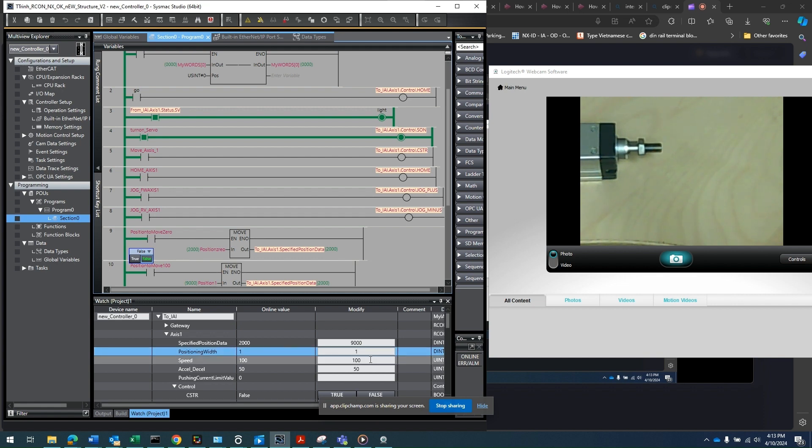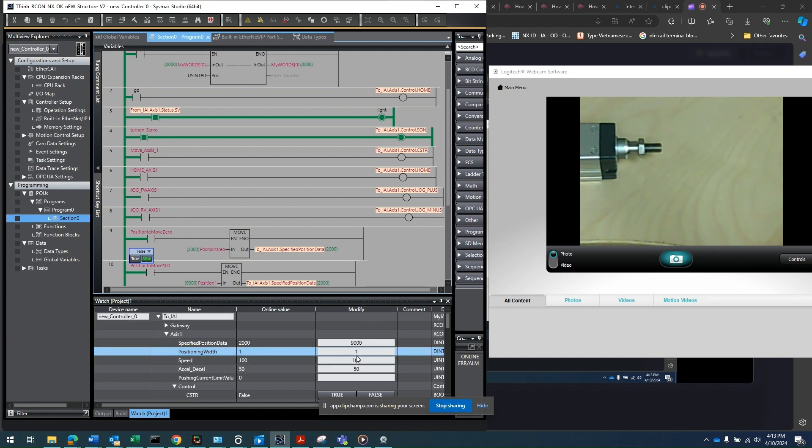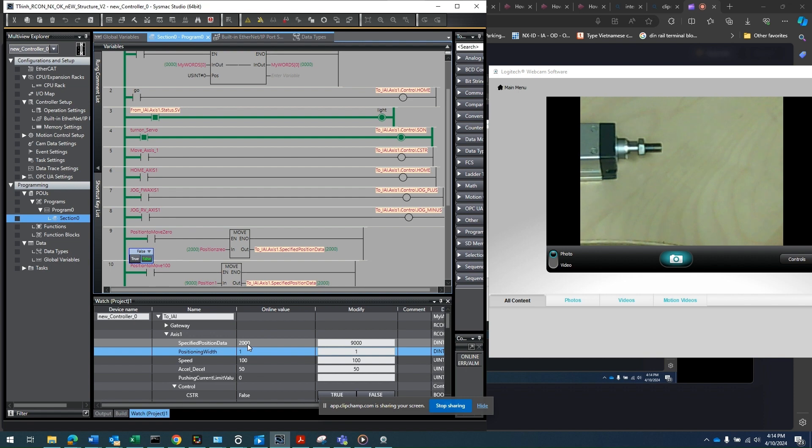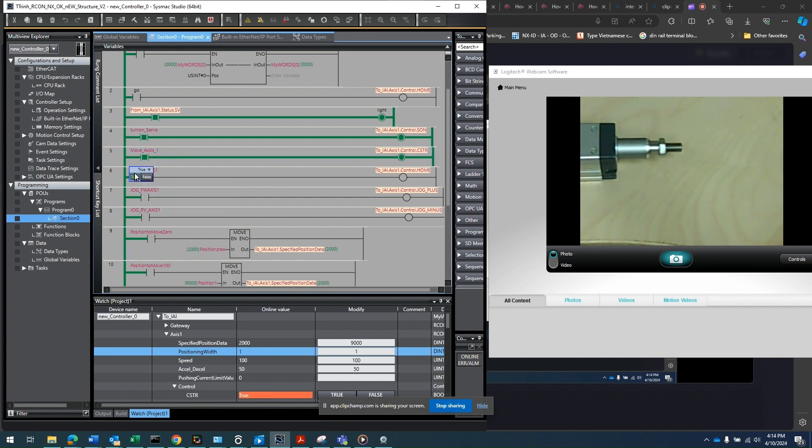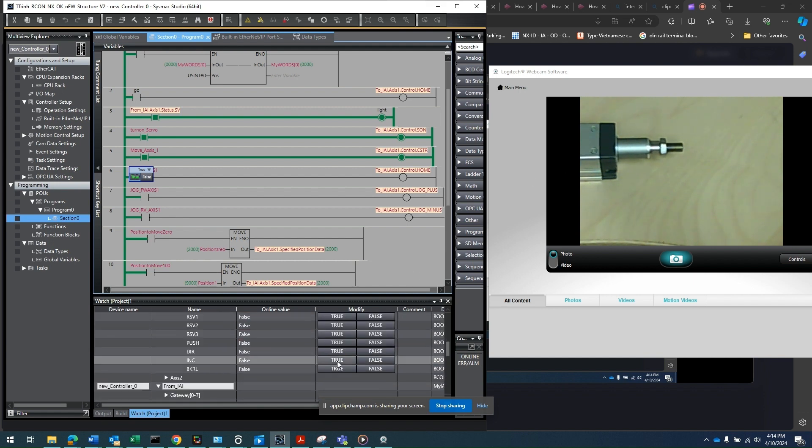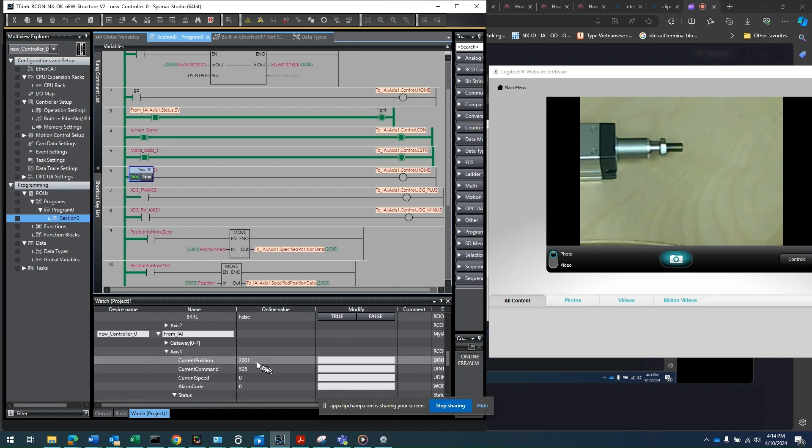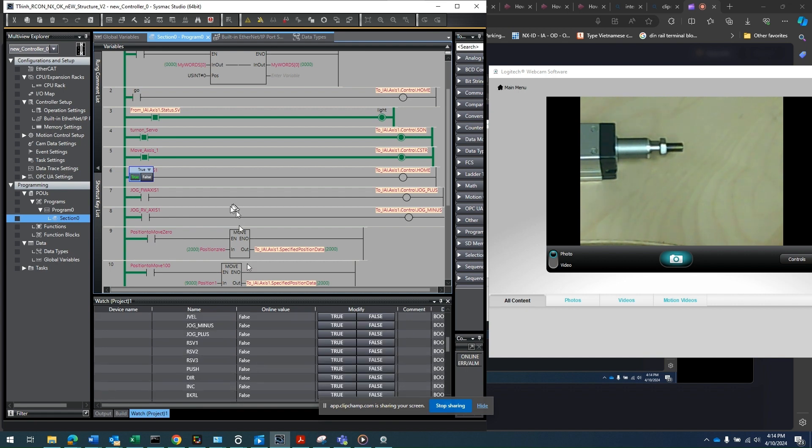You need to have some speed in here. This is in millimeter per second. I have 100 millimeter per second in there. Now I have 50. That means 0.5G. All right, these are the minimum that you need to set up. Okay, so right now the current position is I want to go the position I want to go to is 20 millimeters. So at this point, if I execute this move axis one by turning it on, now it goes to 20 millimeter. And how do I know that? Because if I go down here and look at my status, it shows 20.01 millimeter. Okay, let's say I'm going to turn this bit off for now.